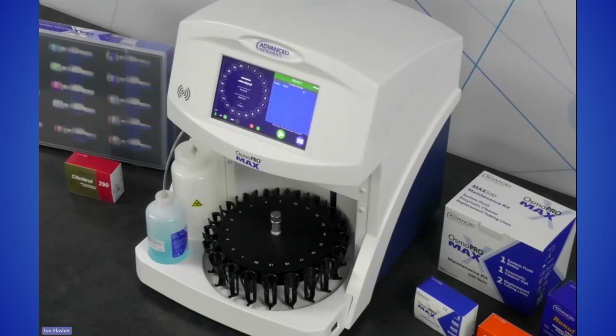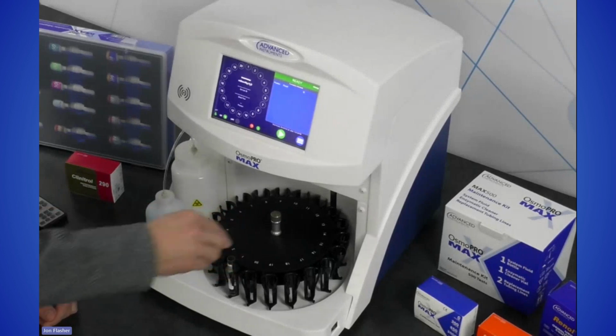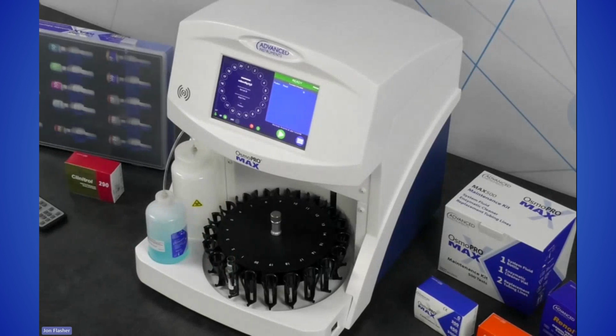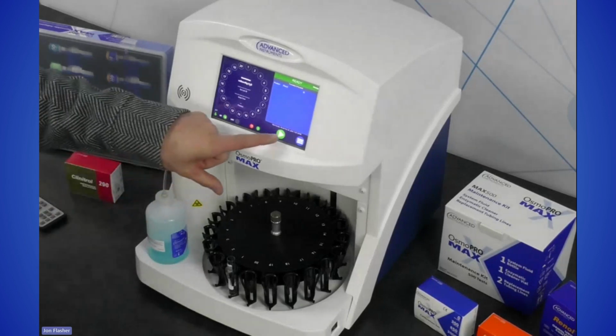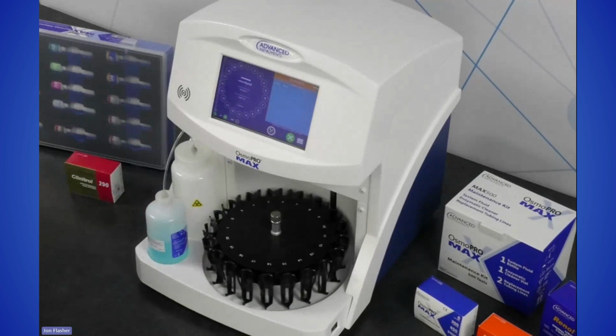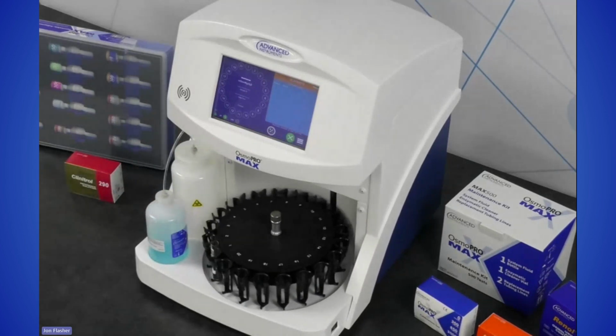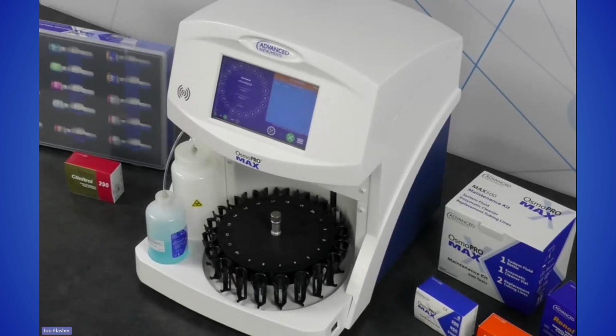So we'll take a different angle here, and I'm just gonna come across the camera here and grab my sample. So again, the turntable really accommodates most primary sample tubes. So it can be your gel separator tubes, your red top serum tubes, most urine tubes that you'll get for collection as well will go in here. And really the primary requirement for loading a tube is just making sure that that barcode is facing out. So when the turntable does turn through, that little black rectangle in the back where the onboard scanner for the turntable lives will actually pick up that barcode and know exactly what sample is in what spot so it can continue testing. So we're going to go ahead and pretend that's our patient sample. We're going to hit play. And it's going to go through and scan each spot starting at position 20. And it's going to keep looking for samples in the turntable.